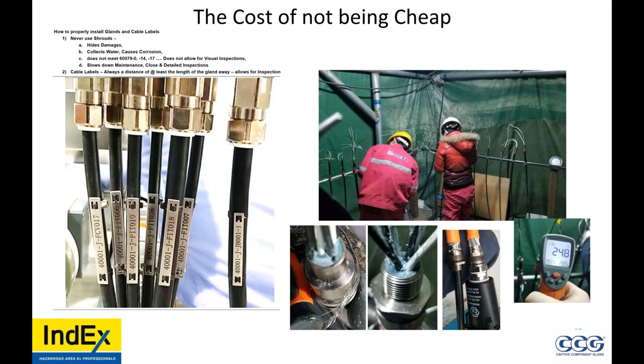Now, what's the easiest way? Well, this is what we at Index do. We create training procedures, methodologies, how best to supervise people. Here we had them doing barrier glands, an assembly line method at 25 Celsius in the room. We made sure that the sheath went right up the gland, up the arm, the sheath covered up the armor, all the way up to the armor clamping ring, not far away, because the back IP seal of the gland would make contact with the armor, but not the sheath.